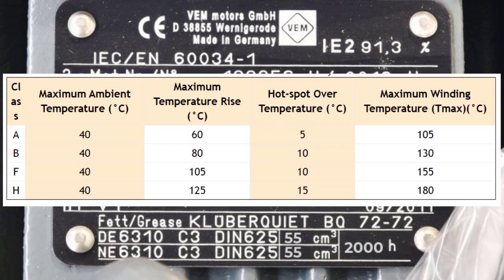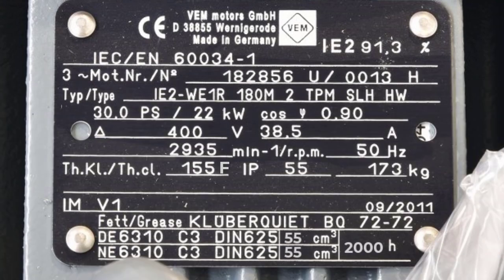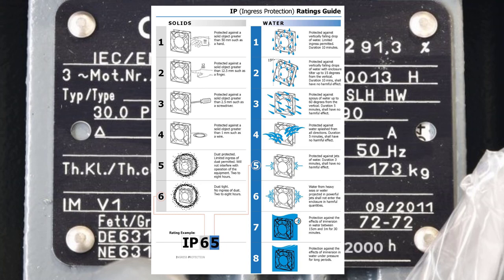The insulation class describes the ability of the motor winding insulation to handle heat, which affects insulation lifetime. There are four classes: A, B, F, and H. In our case, the insulation class is F, meaning the maximum temperature the windings can withstand is 155°C. IP stands for Ingress Protection and has two numbers: the first describes protection against solids and dust, and the second describes protection against water and moisture.